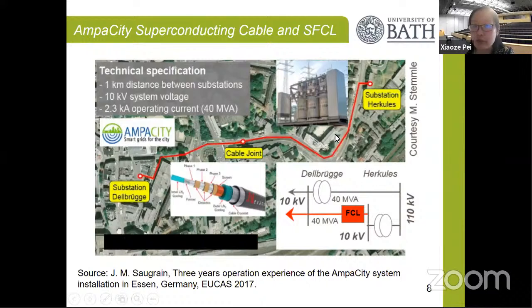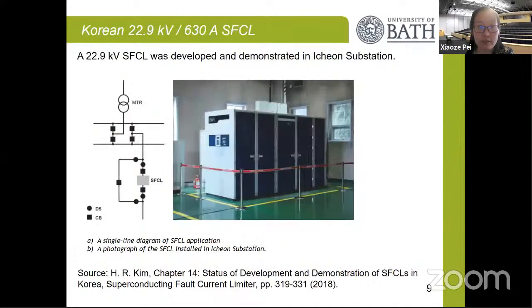So that is why the superconducting cable, which has a very high power density, is able to do the connection at a lower current value, which is 10 kilovolts. So it connects the 2 substations with 1 kilometer of superconducting tape. It also investigates the cable joint, so how to join the 2 superconducting cables together, and the fault current limiter to limit the fault current level for protection purposes. This has been running for a few years now, very successful.